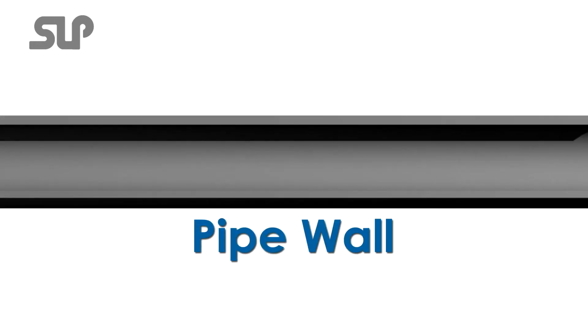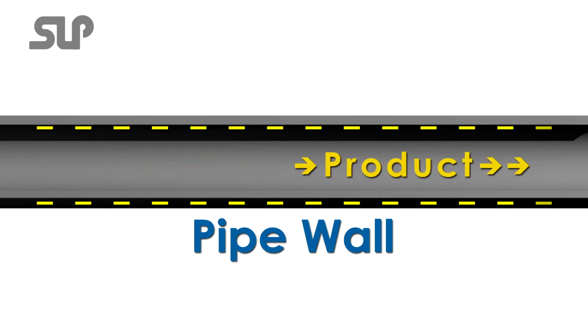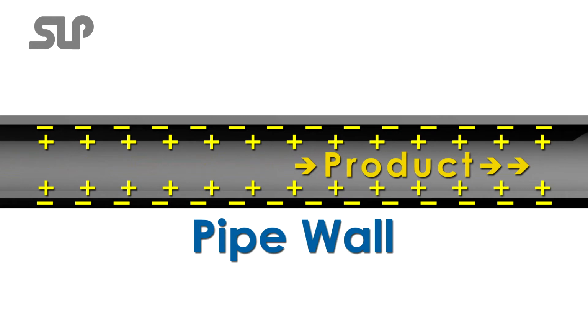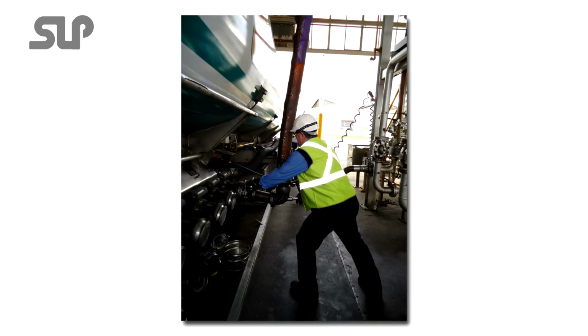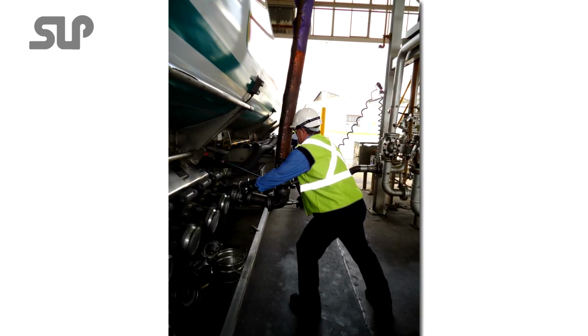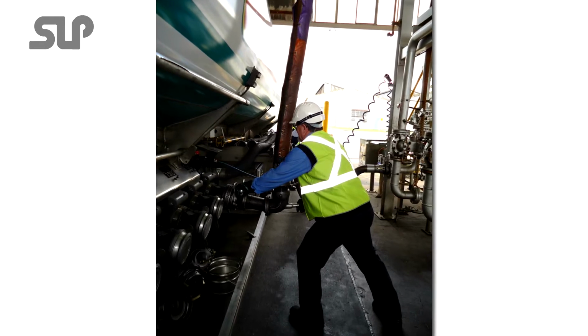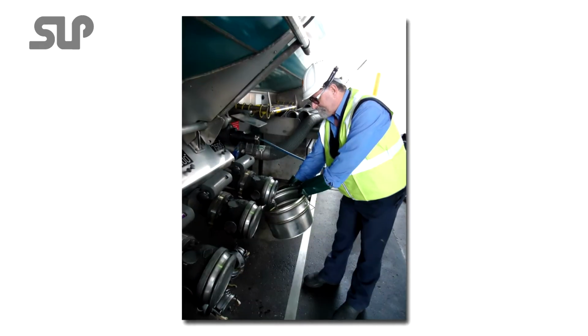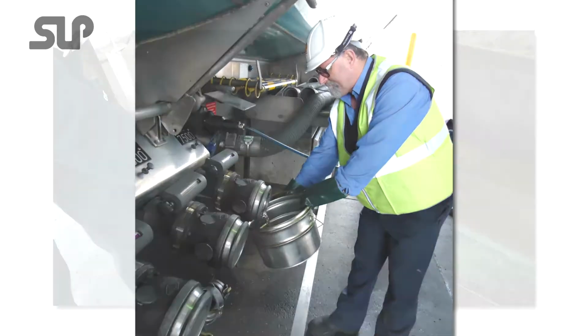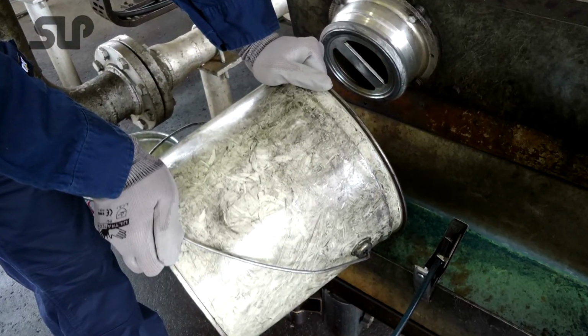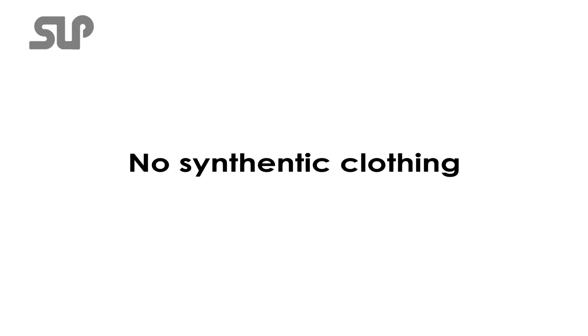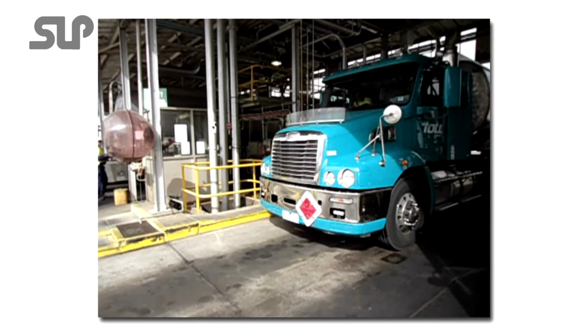Static can be created in many ways, but in the fuel industry, it is most commonly created by the movement or friction produced between the product and the walls of a pipeline, a container, or a tanker compartment. Static occurs in our everyday operations, like when you are loading product into a tanker, draining product into a bucket, pouring product into a drainage tank, when removing clothing or simply wearing polyester or nylon clothing, and static can also be generated from a moving vehicle.